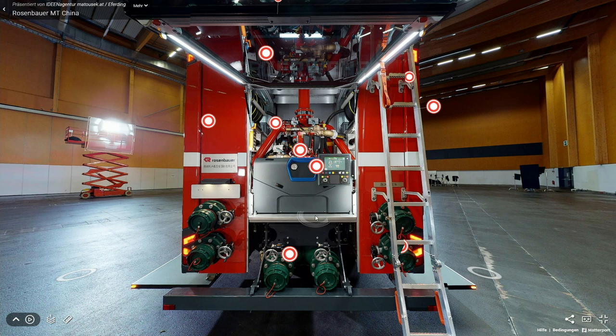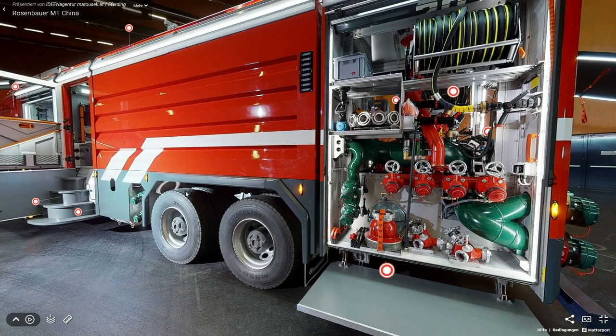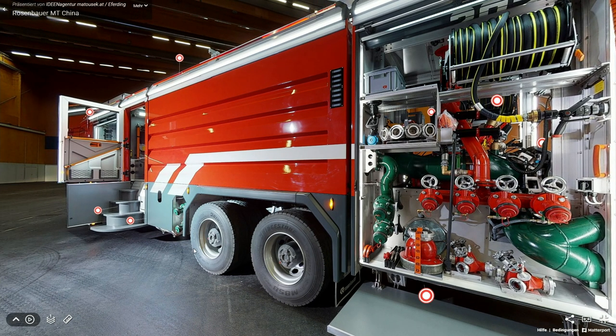This pump is an N130, specially designed for larger tanks and industrial firefighting vehicles. It can handle up to 13,000 liters per minute in tank suction mode and up to 20,000 liters per minute in feed mode. The smaller pump systems, such as the N45 and below, are absolutely identical in construction to those of the AT and CT. Pump systems with capacities of 2,000 to 13,000 liters per minute can be installed in MT vehicles. These pump systems can be combined with different around-the-pump foam proportioning systems such as the Fix-Mix 2.0 or Foamatic, and different direct-injection foam proportioning systems such as Variomatic or Hydromatic, as well as CAFS or compressed-air foam systems. The extinguishing agent tanks can hold volumes between 5,000 and 20,000 liters, designed as pure water tanks, pure foam tanks, or combined tanks, made of polypropylene and suitable for transport of drinking water.